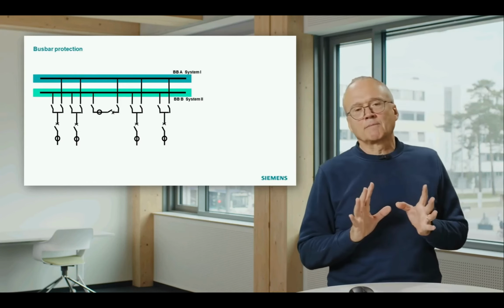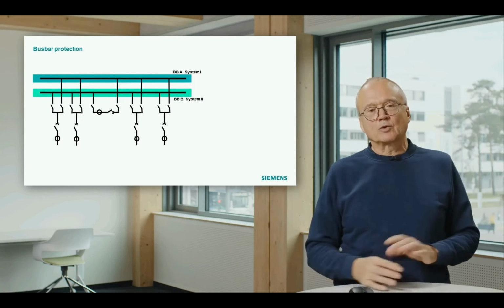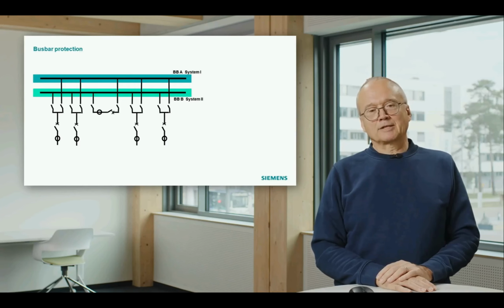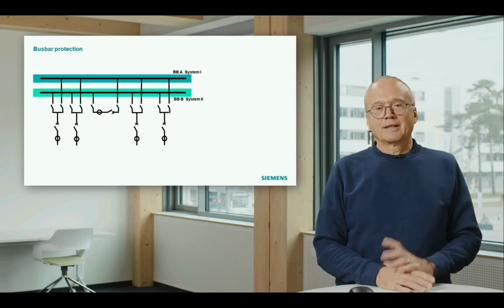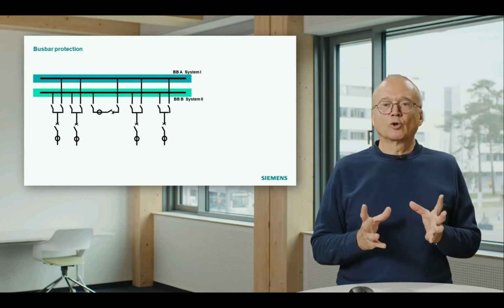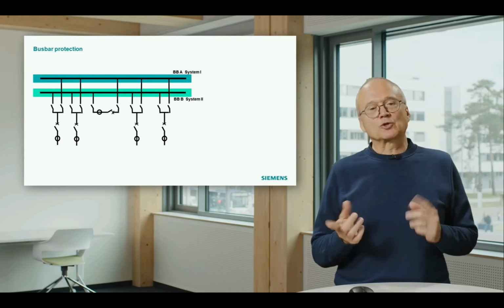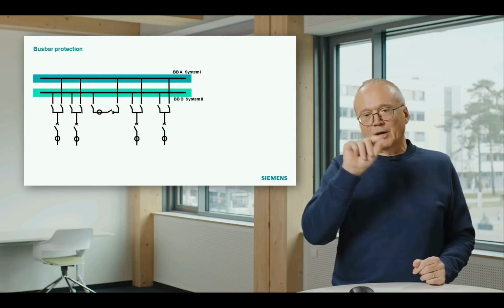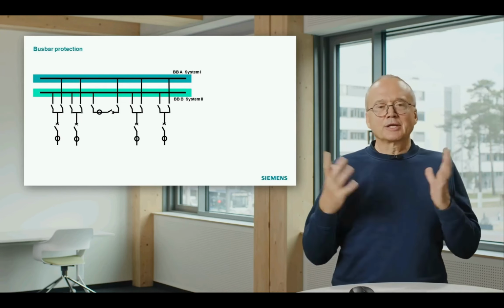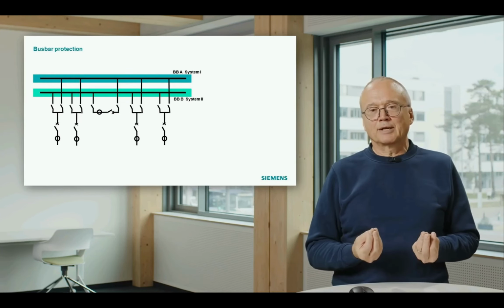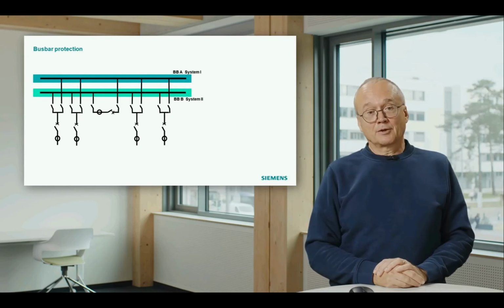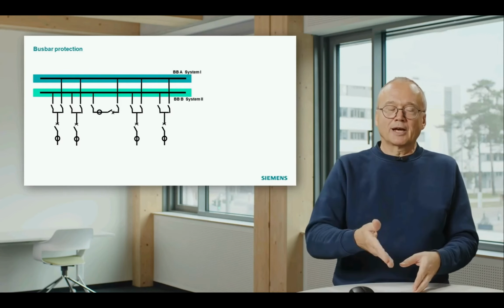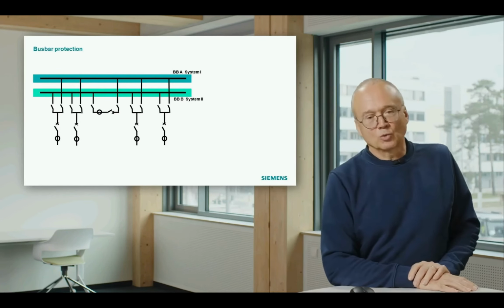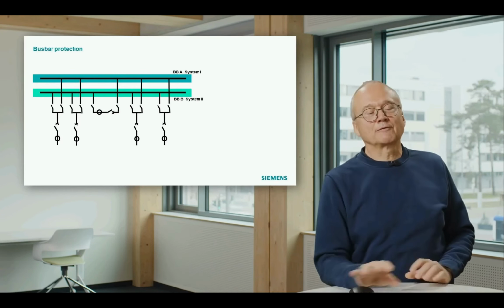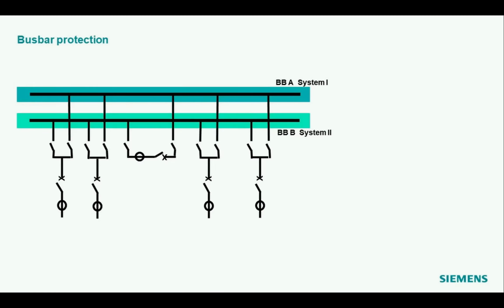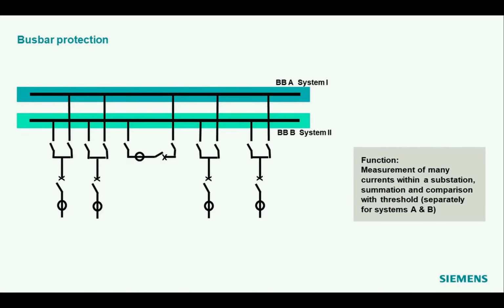That looks pretty trivial in such a small system, but imagine you have a busbar, maybe you have a triple busbar, you have 20 feeders. That means you have a lot of wiring and you have a lot of contacts, and you must also make up your mind what is going to happen if one of these contacts is somehow dirty, defective, or whatever, and you get the wrong topology information. How does it disturb the measurement? Because then you may do a wrong assignment of a measured current to a busbar. And that makes the application of the differential principle a bit tricky in case of the busbar protection.